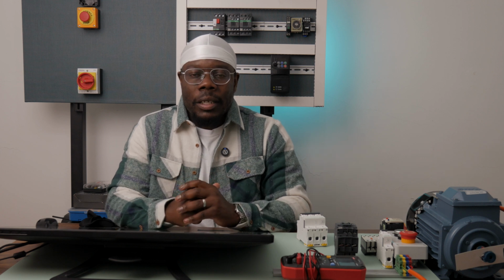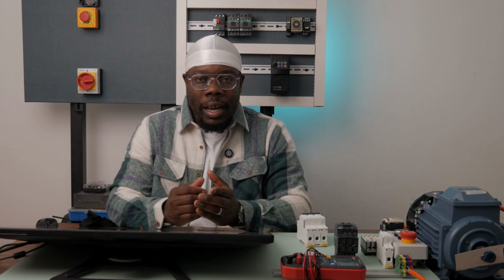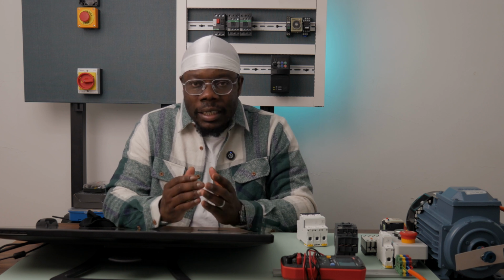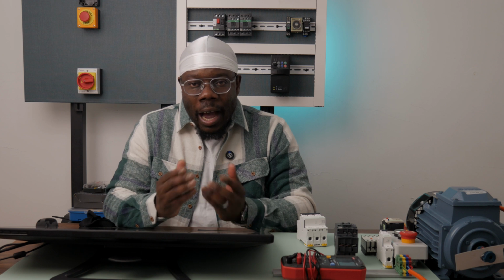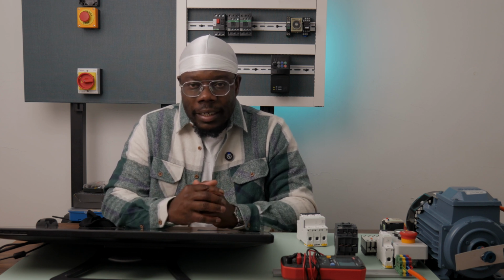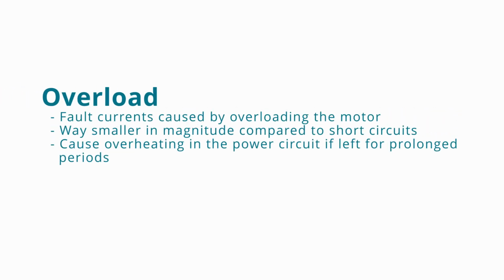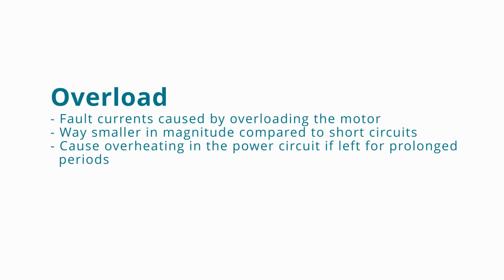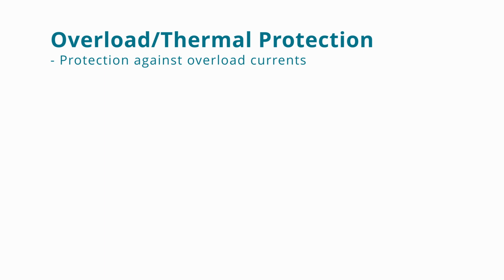After short circuits, we need to protect our electric motors from overcurrents that are associated with overloading the electric motors. Overload currents can lead to overheating of electric motor windings, which causes insulation breakdown of electric motor windings, ultimately leading to short circuits in electric motor windings. Let's define what an overload is. Overloads are fault currents that are caused by overloading the motor. They are way smaller in magnitude compared to short circuits, but they will cause overheating in the power circuit if left for prolonged periods. Protection against overload currents is called thermal protection.